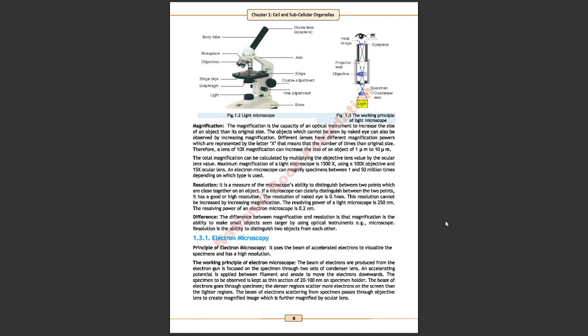The beam of electrons produced from electron gun is focused on the specimen through two sets of condenser lens. An accelerating potential is applied between filament and anode to move the electron downward. The specimen to be observed is kept as thin section of 20 to 100 nanometer on specimen holder. The beam of electron goes through specimen. The denser regions scatter more electrons on the screen than the lighter regions. The beam of electrons scattering from specimen passes through objective lens to create magnified image which is further magnified by ocular lens.